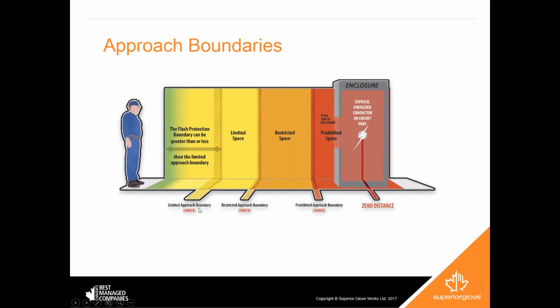To get into this area, a lot more requirements need to be met. It requires the same amount of protection as if the worker were to make direct contact with the machine itself. Only qualified personnel are permitted to be in this area, and they need to have the following things. They need to have the appropriate PPE. They need to have specified training on work for energized equipment. They need to have a documented plan justifying the need to perform work on energized equipment. Anyone in that area must obtain a risk assessment to cross the prohibited boundary.